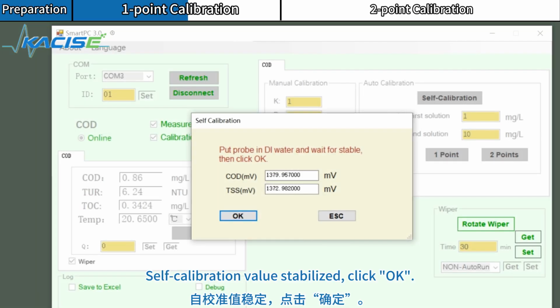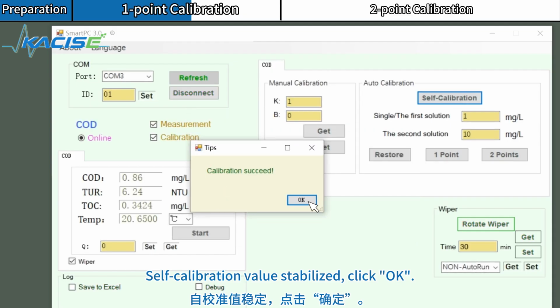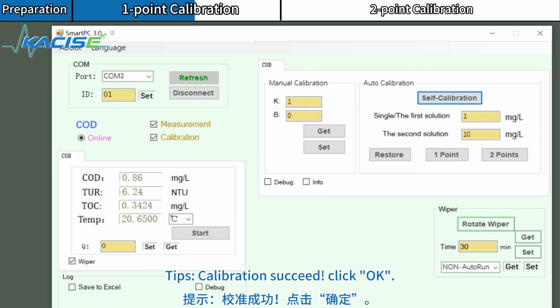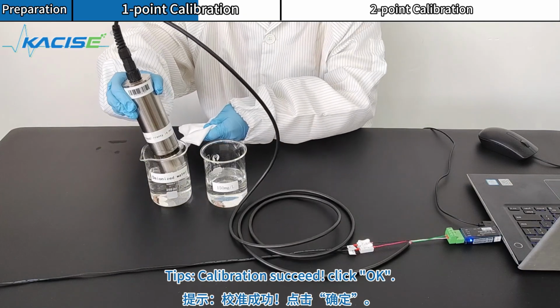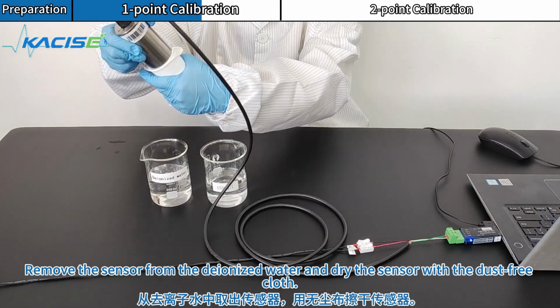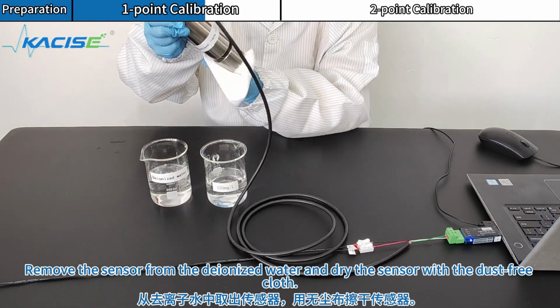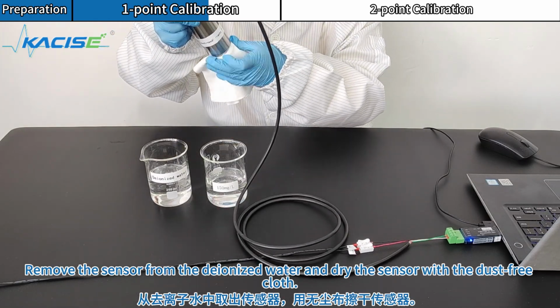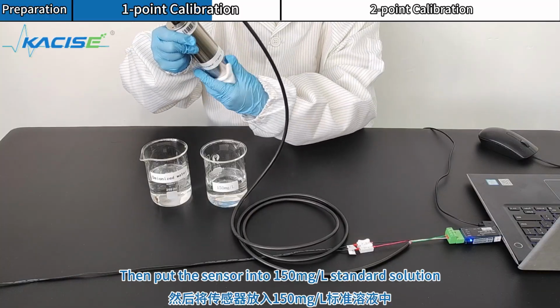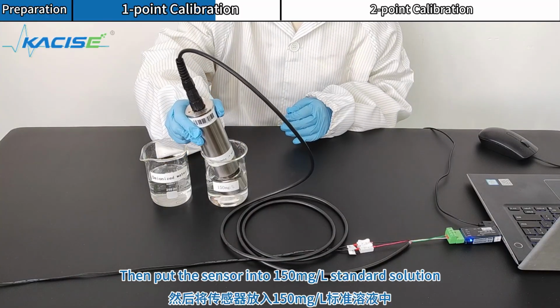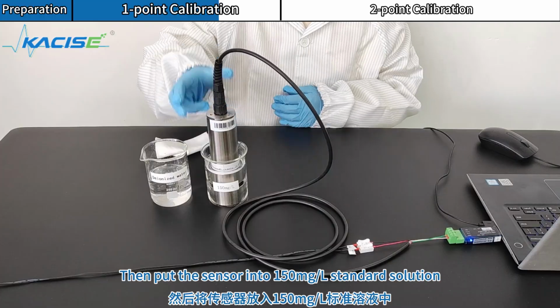Self-calibration value stabilized. Click OK. Tips: calibration succeed. Click OK. Remove the sensor from the deionized water and dry the sensor with the dust-free cloth. Then put the sensor into 150 milligrams L standard solution.